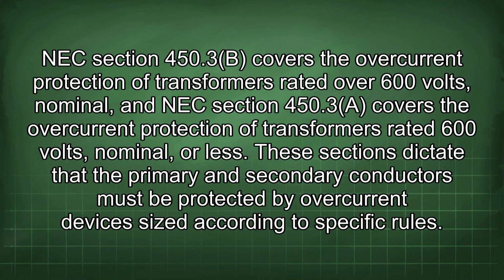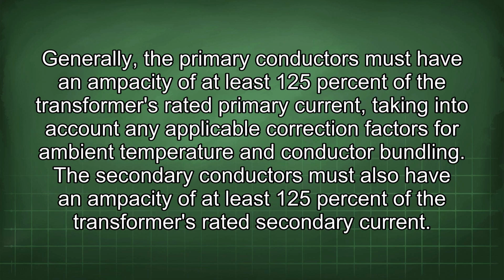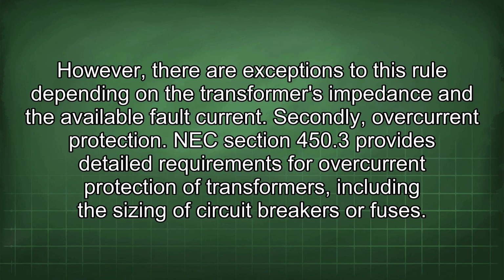These sections dictate that the primary and secondary conductors must be protected by overcurrent devices sized according to specific rules. Generally, the primary conductors must have an ampacity of at least 125% of the transformer's rated primary current, taking into account any applicable correction factors for ambient temperature and conductor bundling. The secondary conductors must also have an ampacity of at least 125% of the transformer's rated secondary current. However, there are exceptions to this rule depending on the transformer's impedance and the available fault current.